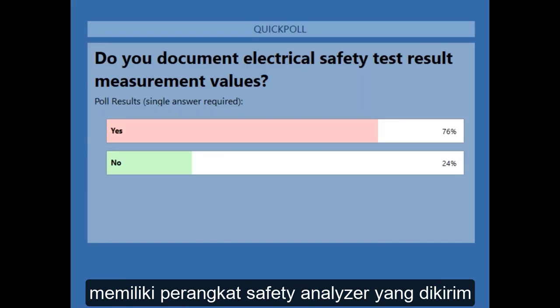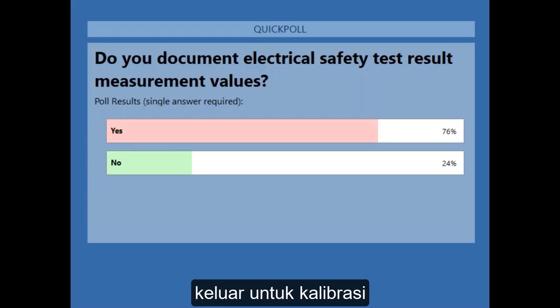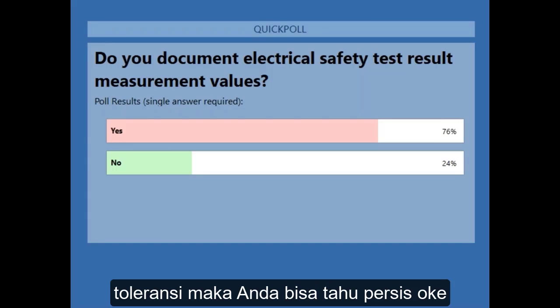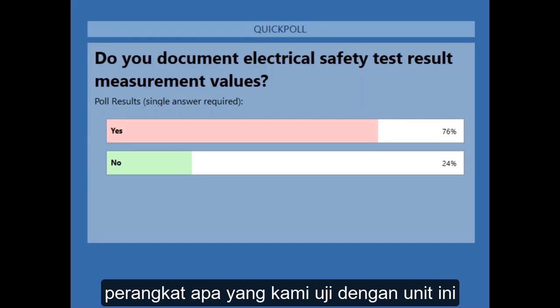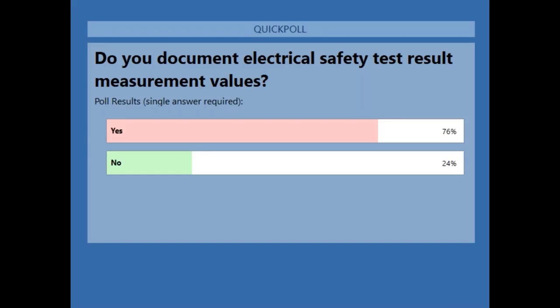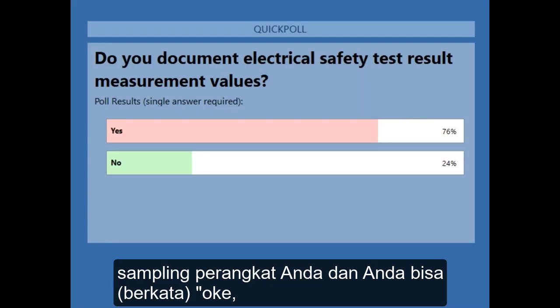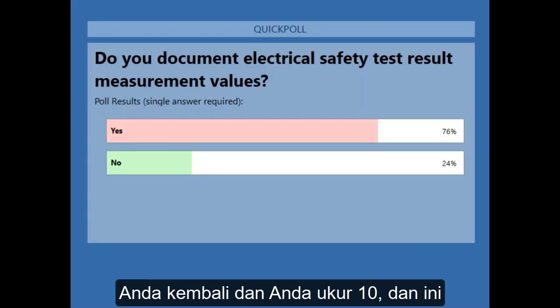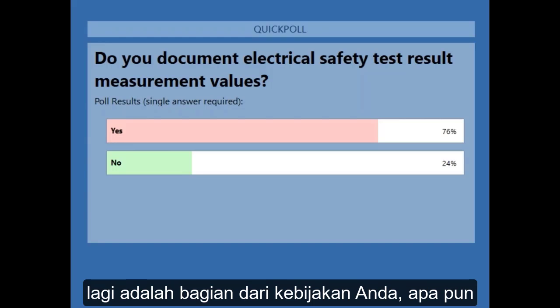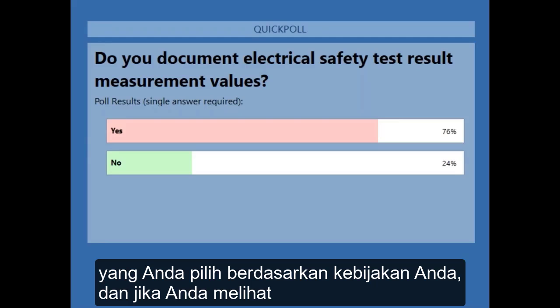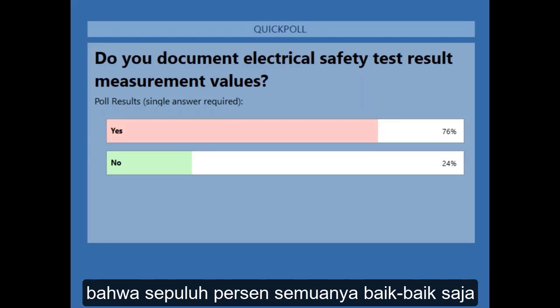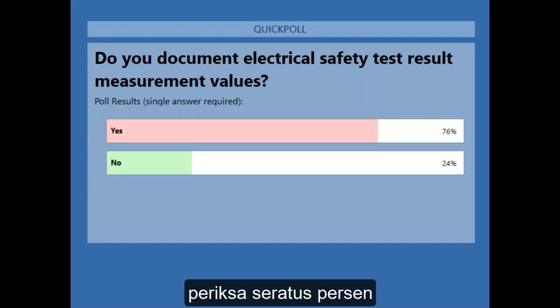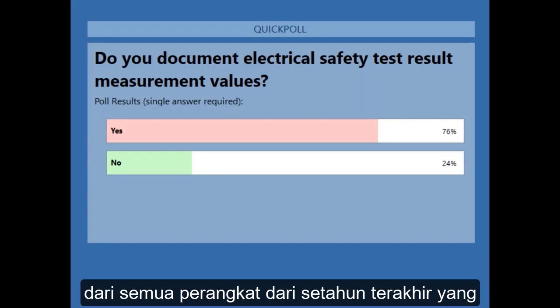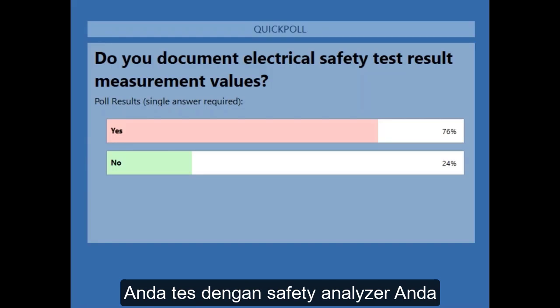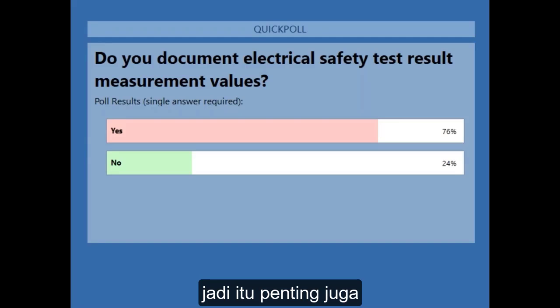That way, if your safety analyzer goes out for calibration and it comes back out of tolerance, you can know exactly what devices we tested with this unit. Then you can go back and do a sampling of your devices, say 10%, and this will be in your policy, whatever you choose. If you see that at 10% everything is good, maybe you don't have to go back and check 100% of all the devices for that last year that you used your electrical safety analyzer on. So that is important as well.